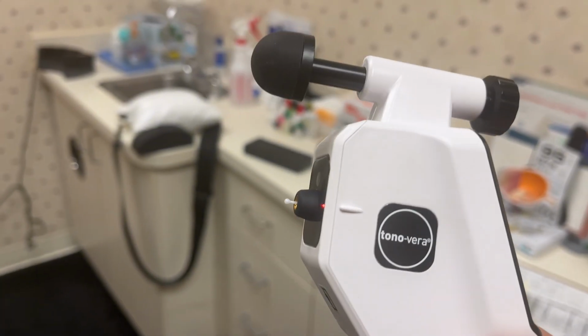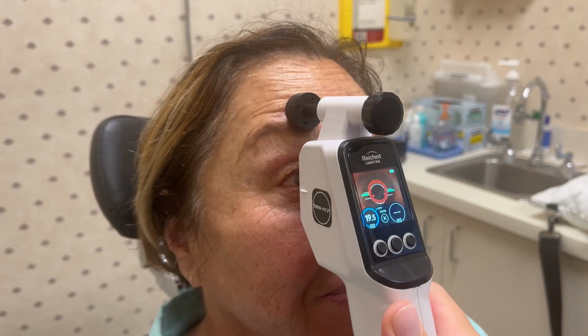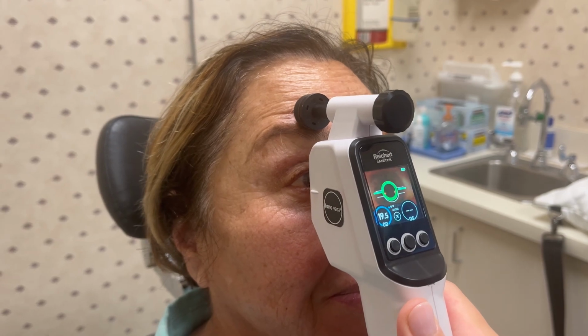And the last method is called a rebound tonometer. This is a newer device made by Icare and Reichert that basically uses a tiny little probe that will flick in and out. It's so gentle on the eye that you really don't need topical anesthetic, and based on the force of the rebound of that little probe shooting in and out, again very gently, it will give us a reliable pressure. Again, it's really helpful in on-call environments or if you're traveling, because you don't need all the expensive equipment of a slit lamp to check someone's pressure.